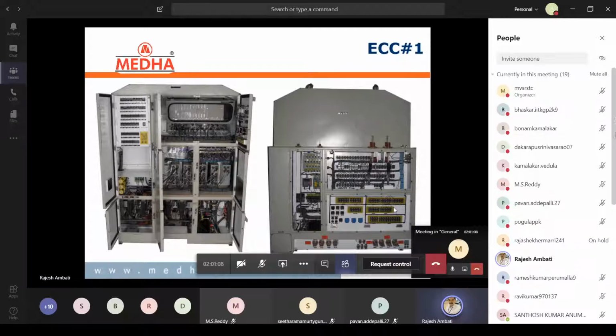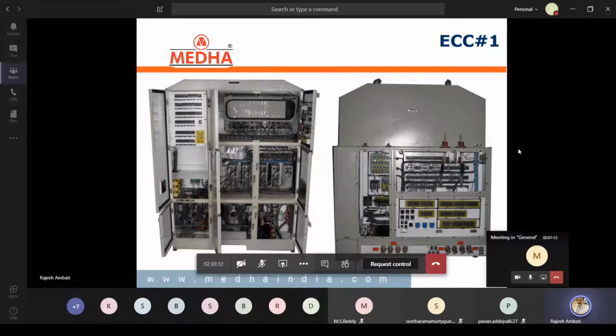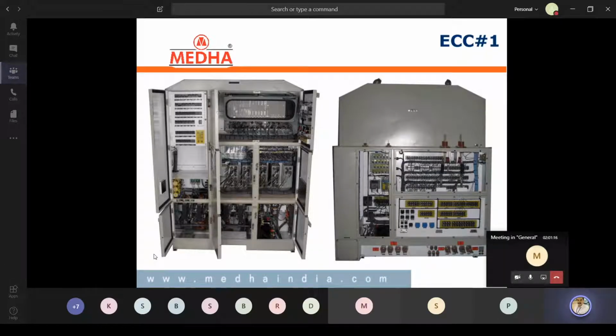And on the back side, these are the terminal connections. All of these 3 subassemblies, ECC 1, 2, 3, are pressurized cabinets, completely airtight, so an air filter is there, and inlet air is given from the bottom through the TM blower connection. Internally we can find the DC link voltage sensor, which is now shifted to this side, pressure switches, connections, and all placed here.